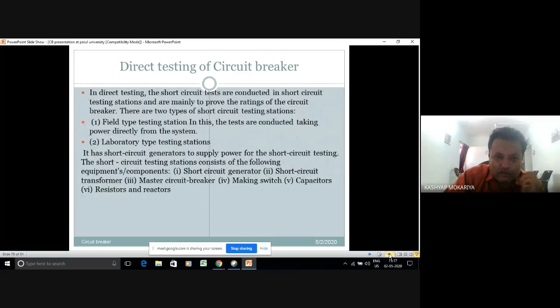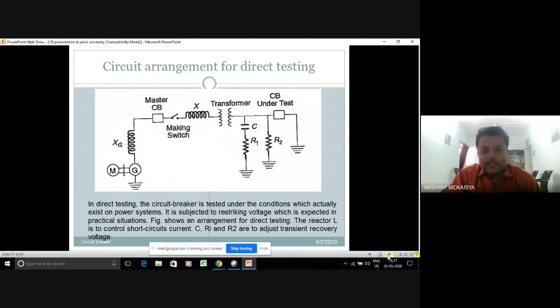In direct testing, the short circuit tests are conducted in a short circuit testing station, either a field type station or a laboratory type station. It has various elements: short circuit generator, short circuit transformer, master breaker, making switch, capacitors, resistance, and reactance. So this is a layout. Now you can see if your breaker fails while testing here, immediately the master breaker should come into the picture.